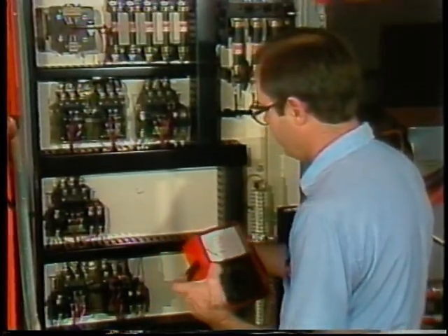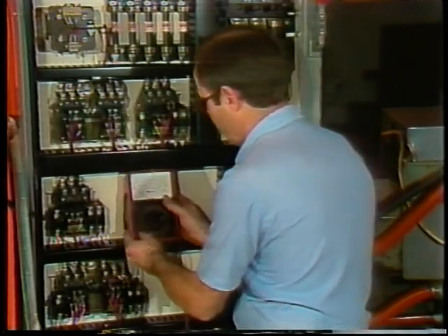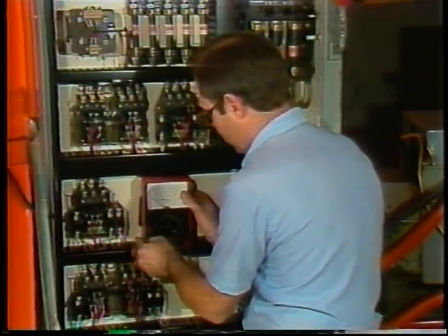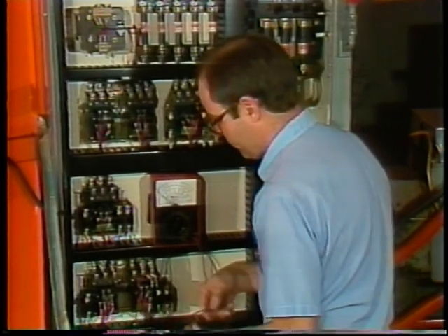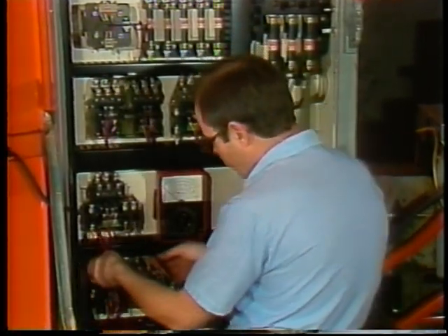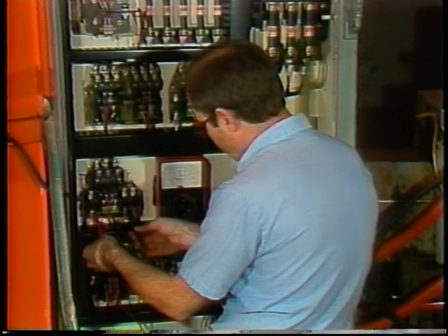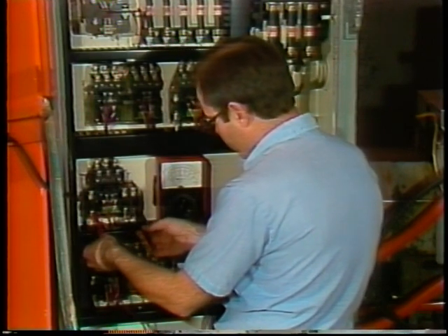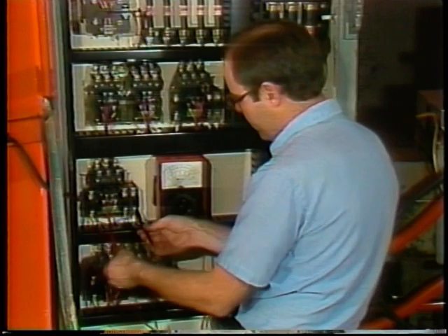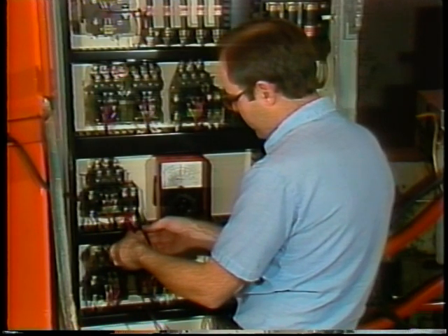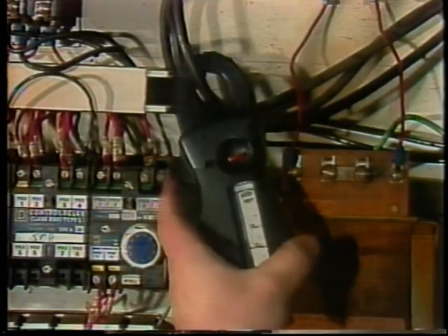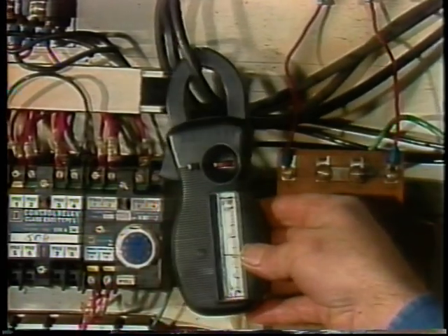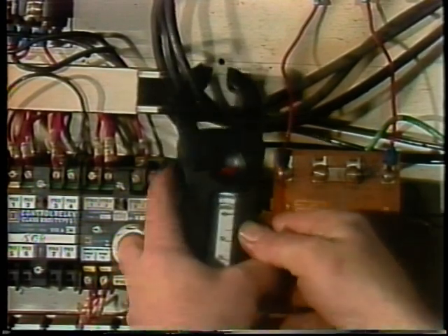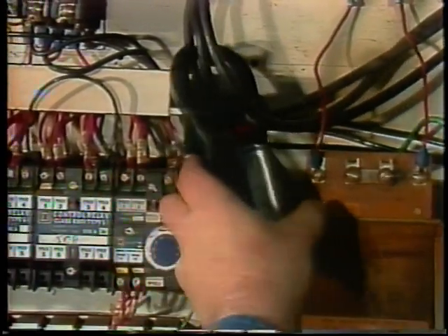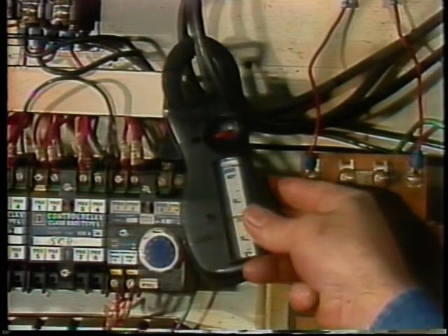Other checks include measuring the voltage at the operating motor. If the voltage on one or more phases is lower than normal for any reason, the motor will overheat. Induction motors are particularly sensitive to low voltage and will sometimes stall completely if the voltage drops as little as 20%. Current readings are also useful. If the current in all lines to the motor is high, the motor is overloaded. If the current in only one of the power lines is high, with normal voltages, suspect an electrical problem in the motor.